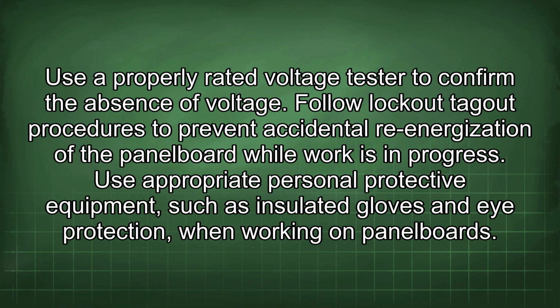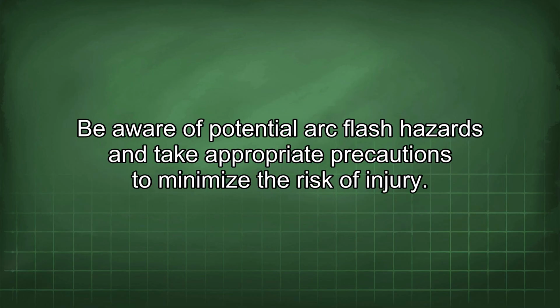Use a properly rated voltage tester to confirm the absence of voltage. Follow lockout-tagout procedures to prevent accidental re-energization of the panelboard while work is in progress. Use appropriate personal protective equipment, such as insulated gloves and eye protection, when working on panelboards. Be aware of potential arc flash hazards and take appropriate precautions to minimize the risk of injury.